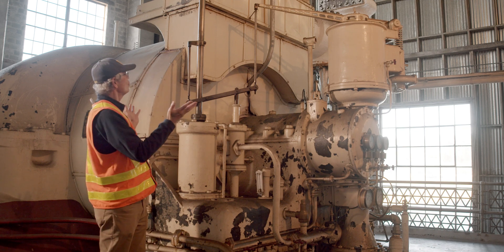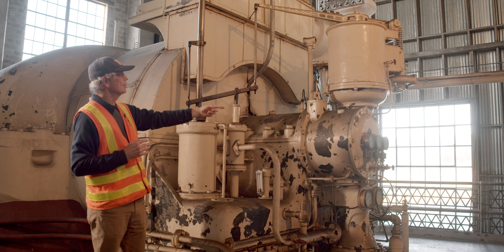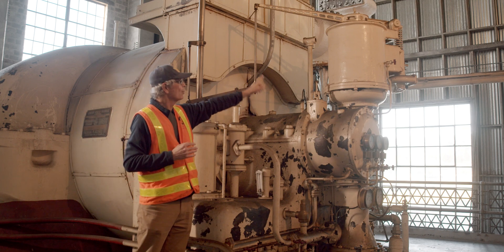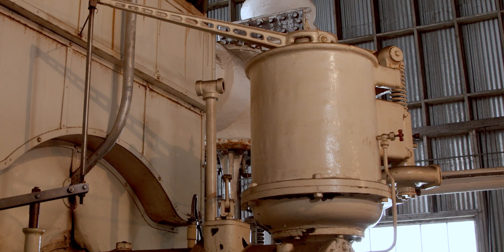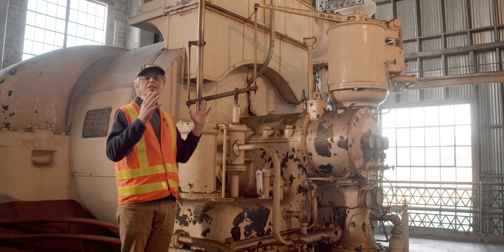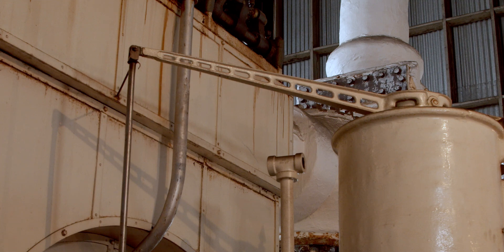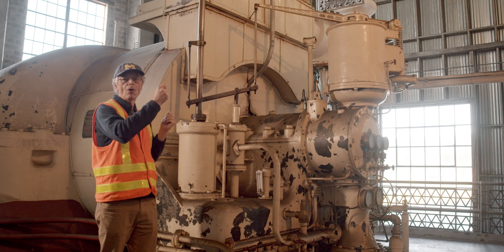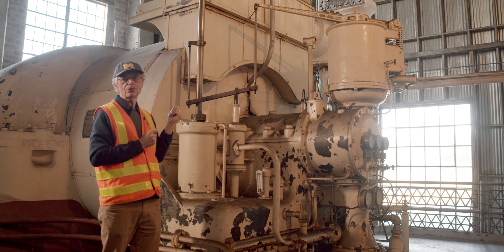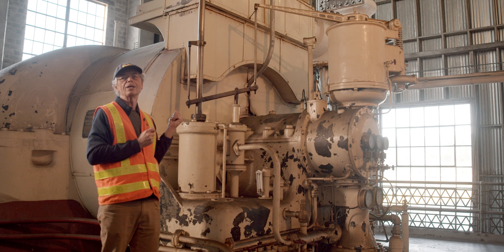Now we have to control this whole thing. The shaft that comes out at the end of the turbine here has a worm, and revolving inside that cylinder is a fly-ball type governor that senses the speed of the machine. Through that arm linkage and this linkage here, it controls the opening or closing of the control valves in order to keep a constant speed or a constant load on the turbine.